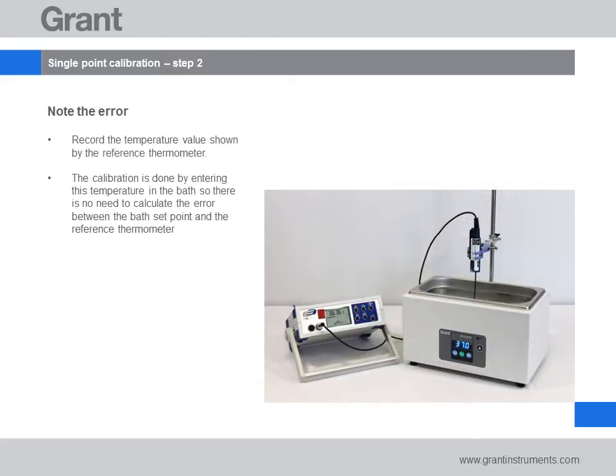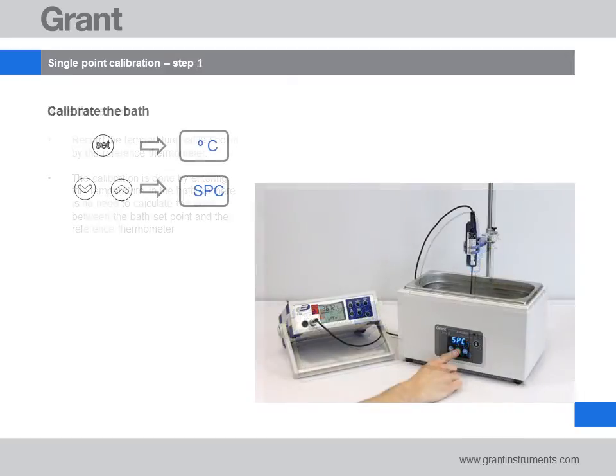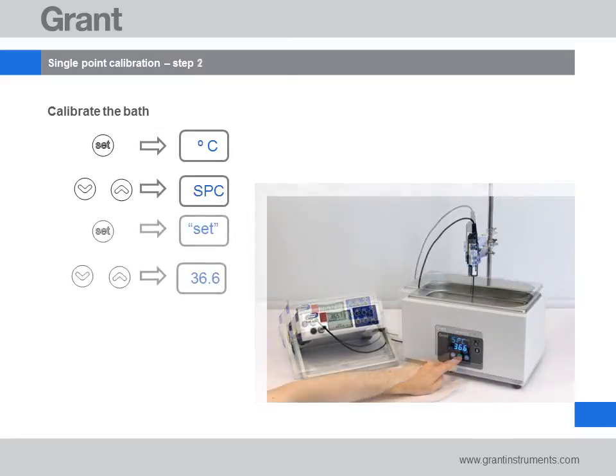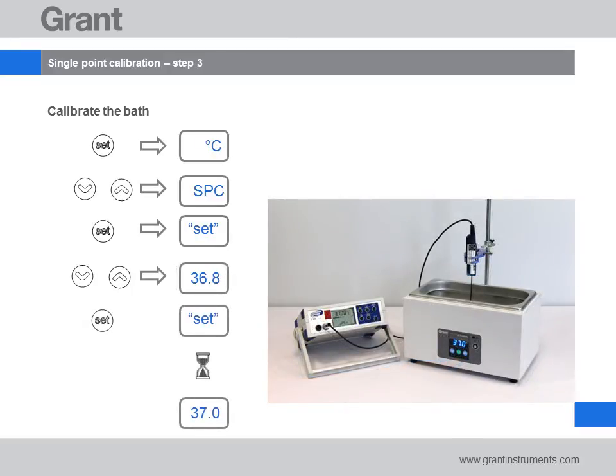The next step is to record the reference thermometer temperature and enter the temperature into the calibration menu. To do this, press the Set button and, using the up and down keys, navigate to the screen displaying SPC. Press Set and then enter the reference thermometer value using the up and down keys. Press Set to enter the value and wait for the bath to automatically adjust to the set temperature. This now completes a single point calibration.